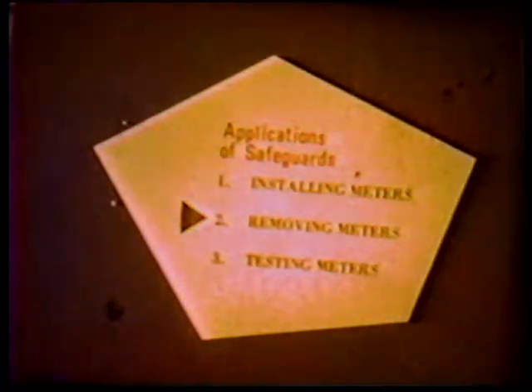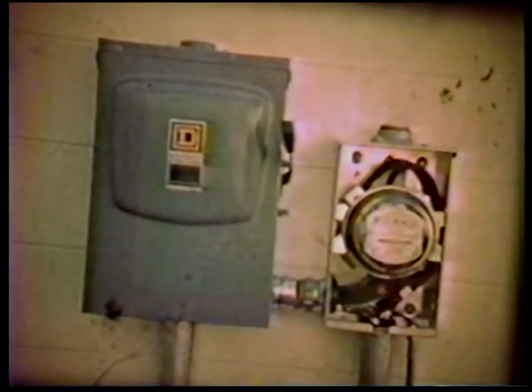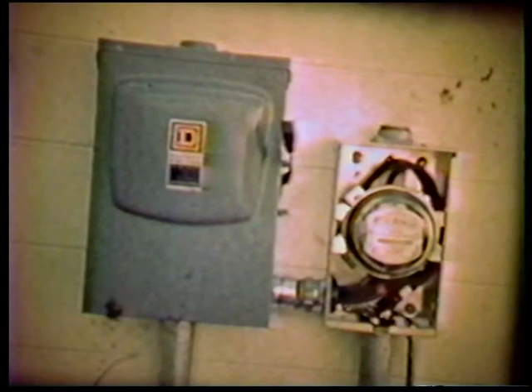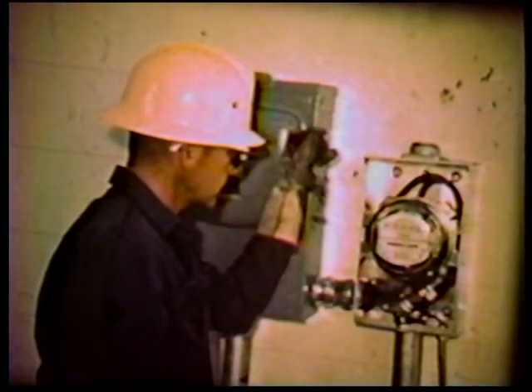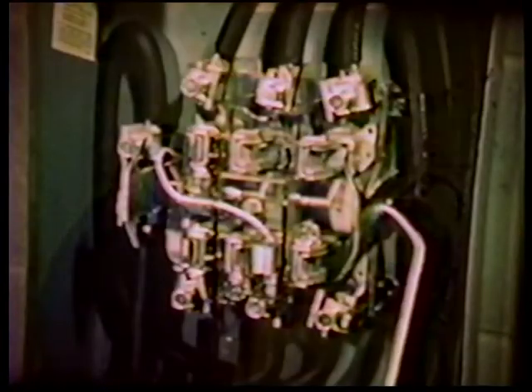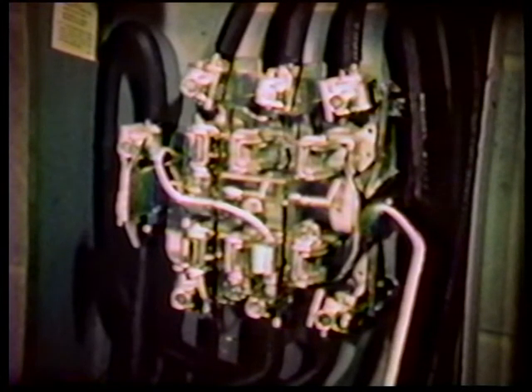When removing meters, there are two different situations you will encounter. One is a meter to be removed under normal conditions, such as a routine change-out for a shop test. The second is a meter to be removed where trouble is suspected. The normal procedure includes a visual check of the cabinet for unusual conditions, a close inspection of the meter to check its condition, and then removal of any heavy load flowing through the meter. Many recent installations are equipped with lever-operated bypass switches, which allow the load current to be shunted around the meter, so that the meter can be removed safely without interrupting service to the customer.